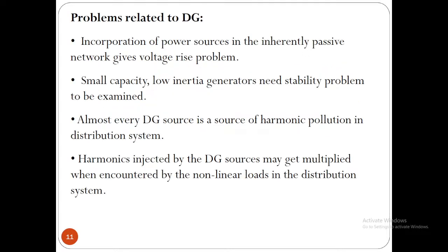So the problems related to DG: the first one is that incorporation of power sources in an inherently passive network gives a voltage rise problem. Whenever you are injecting power, in many cases there is a voltage rise, so that has to be controlled. This is a very inherent problem. Whenever you are feeding power, there is a voltage rise.